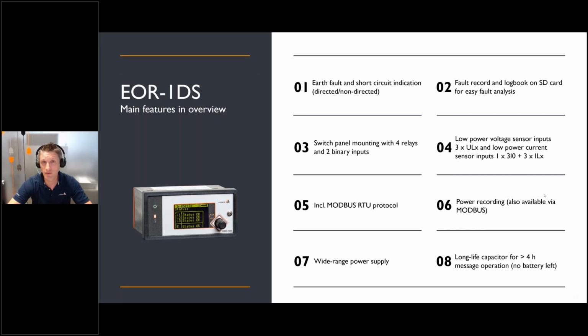The device also has directed and non-directed earth fault and short circuit indication, and has fault records and logbook functionality on board. The fault records and the logbook are saved on the internal SD card, and you can easily dismantle the front plate with this screw. Behind the front plate, you find the SD card. So if you're interested in a certain fault record or logbook, you can take this SD card and view the fault record and logbook on your PC.